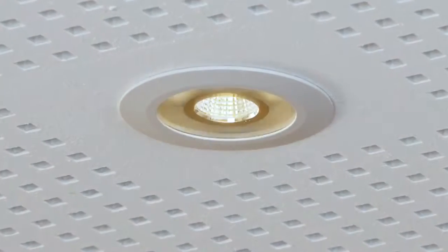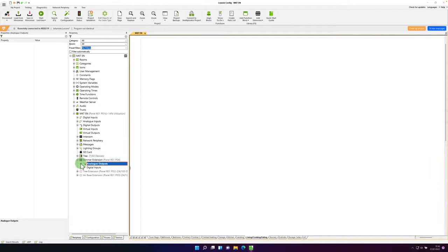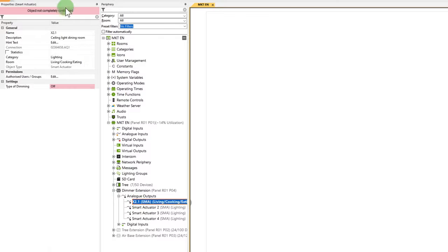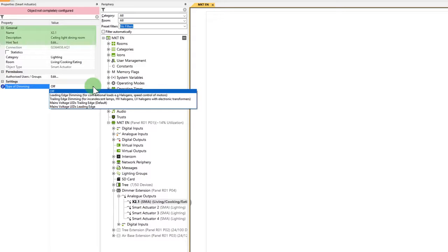We continue with our pendant lights, which are integrated via the dimmer extension. Whenever you're integrating lighting via the dimmer extension, you'll have to work carefully. A dimmer extension has 4 dimming channels. Here, it's important to know which output on the dimmer extension in the distribution board each lighting circuit is wired back to. As in our previous video in this series, you would have already ensured the suitability of any light that you're using in terms of the project requirements and dimming capability.